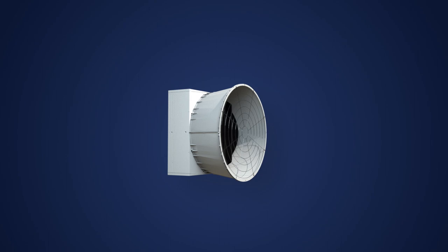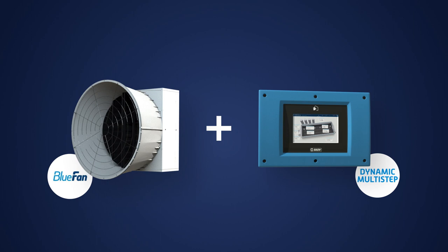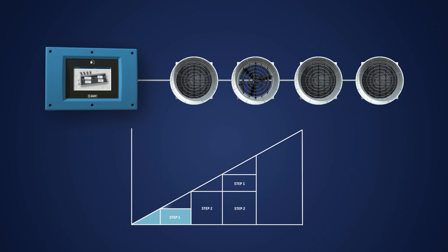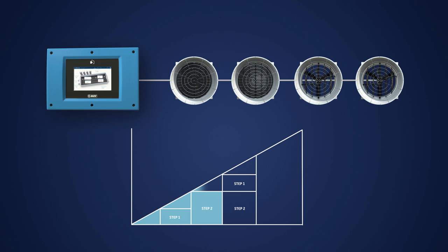The BF50 can be regulated according to the dynamic multi-step principle. Dynamic multi-step is unique in that the fans connect in steps until 50% of their output. When additional ventilation is required and all fans in the section have been switched on and reached 50%, the fans are regulated in parallel up to 100%.